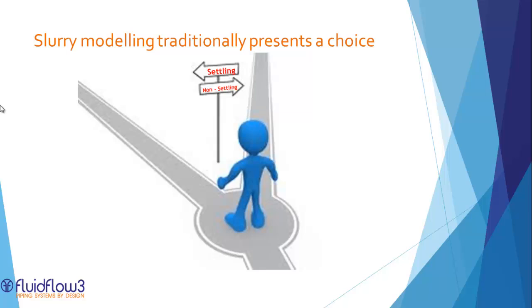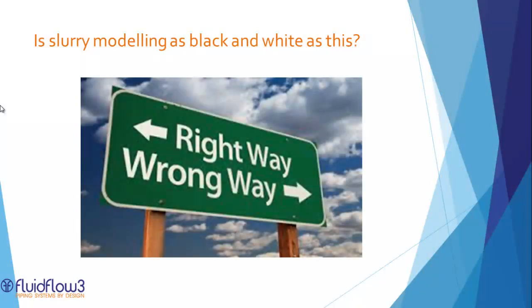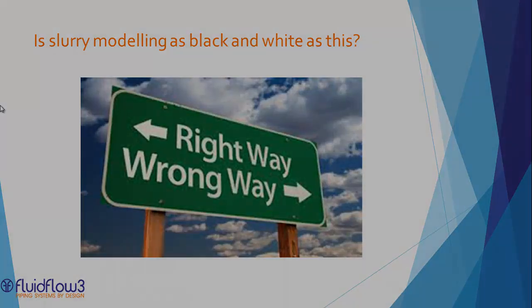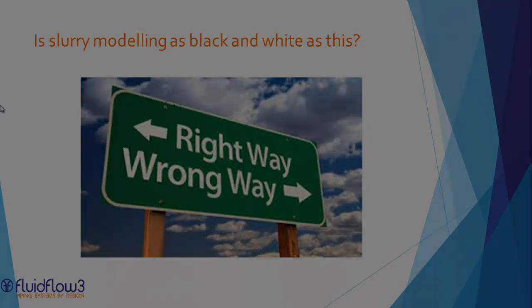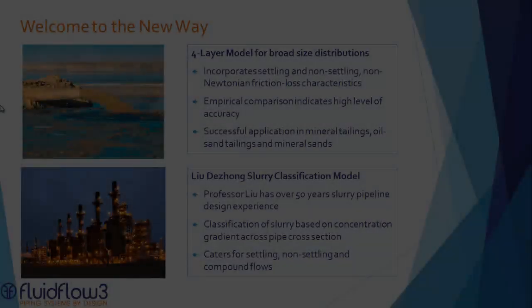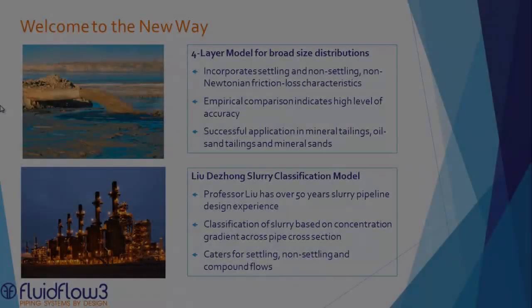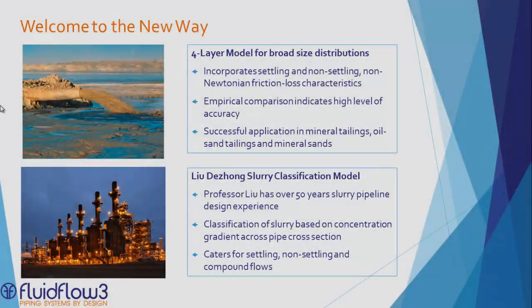Until now, slurry modeling software has forced the designer to make a choice: to model the slurry as a heterogeneous settling slurry, or as a non-Newtonian non-settling slurry. Slurries are rarely as black and white as this. In reality, slurry systems often behave as a combination of these two flows. Broad size distributions and variation in slurry composition due to process instability lead to situations where the friction loss associated with both slurry classifications must be considered.